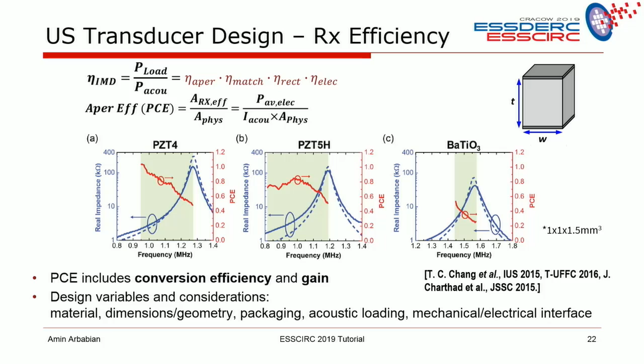Now, what are the design variables? When we design antennas, it's mostly about geometry. Here, geometry plays a role, so dimension and geometry play a role, but there's also material, which has very different properties when you go from one material to the next. If you compare single crystal and piezo, for example, compared to barium titanate, the speed of sound, the coupling efficiency, the K31, the dielectric constant—all of those are going to be very different. So material, dimensions and geometry, packaging, acoustic loading, and mechanical and electrical interfaces—these are the design variables.